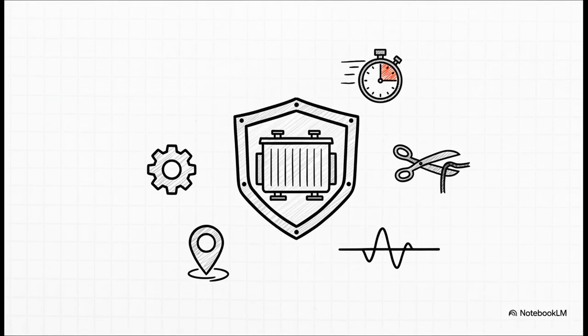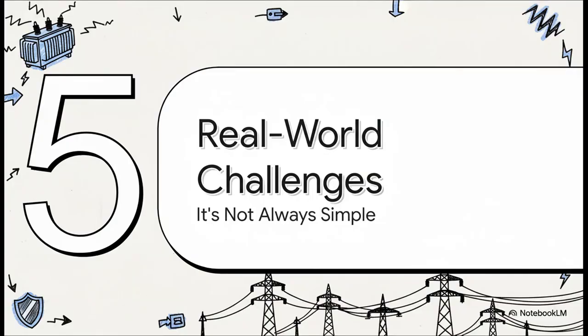And that's why this method is just so brilliant. It's incredibly fast, which means way less damage to the equipment. It's surgical. It only operates for faults inside its zone, which helps keep the rest of the grid stable. And because it's so specific, it doesn't need to check with anyone else. It sees an internal problem, and it acts. Period. Okay, so that all sounds pretty perfect, right? Almost too easy. And, well, you'd be right.